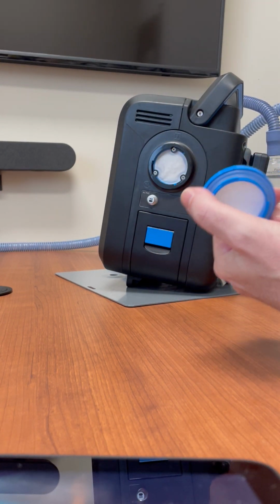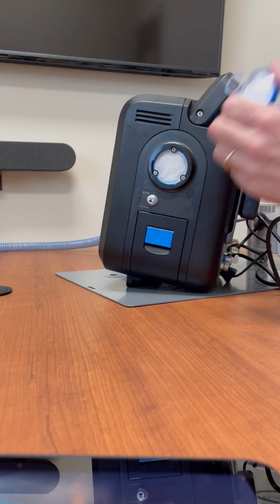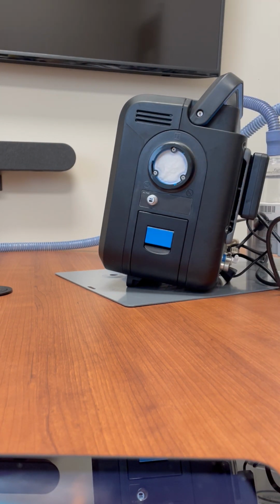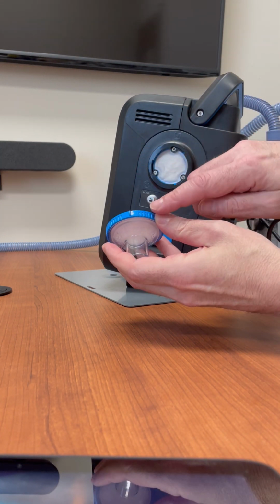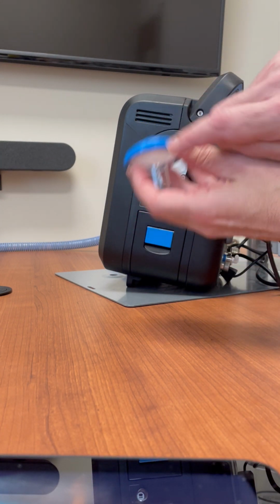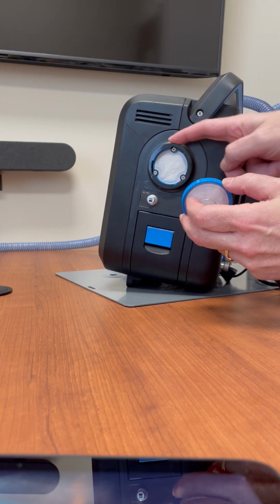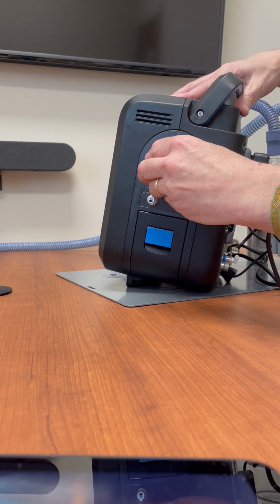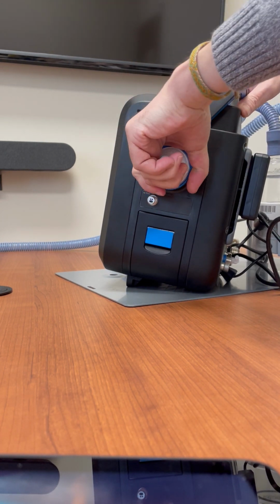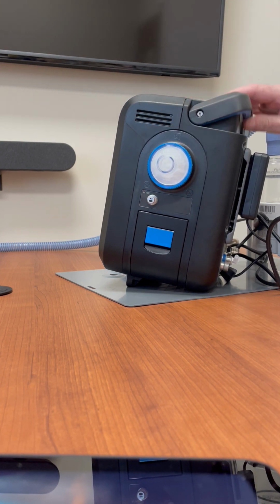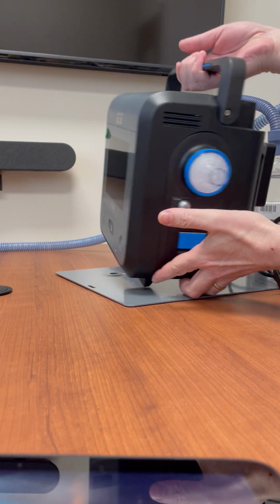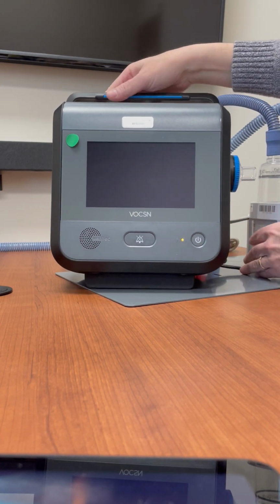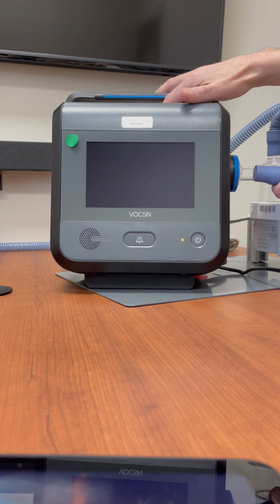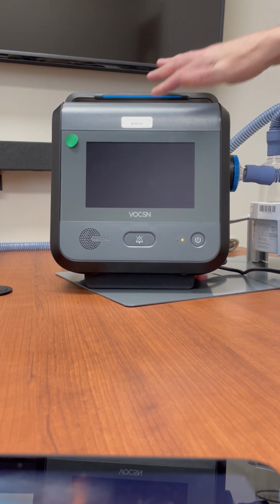So let me take it off first to show you. This is a proprietary filter that only works with this device. It is the only filter that can work with this device. On top of the filter is a little blue notch, and there's a little notch on top of the opening in the vent. So simply line up those notches and turn clockwise a quarter of a turn until you feel it seat into place. And this is where we would plug in the circuit that eventually goes to the humidifier and then to the patient's mask.